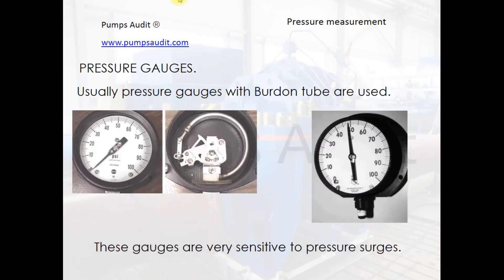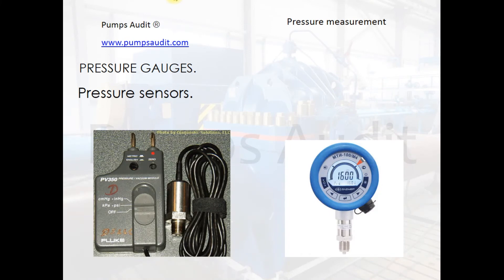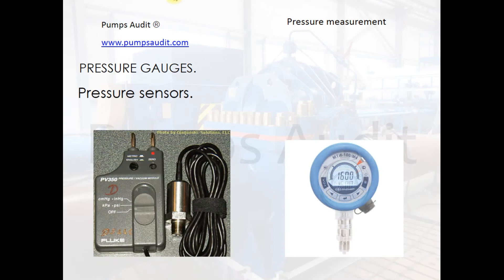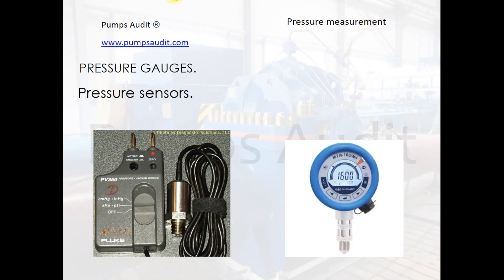Pressure gauges with Bourdon tubes are usually used. The Bourdon-type pressure gauge works on the principle that the curved tube tries to straighten itself out when pressurized, and this motion is mechanically transferred to a hand that indicates the pressure. The main disadvantage of this type is its sensitivity to water hammer and over-pressure. Even calibration doesn't guarantee reliable readings. The preferred type is a pressure transducer such as the Fluke meter, which is calibrated and gives a reading in chosen units when connected to a multimeter. It is important to use a reliable pressure meter and not rely on fixed installed Bourdon-tube type meters.